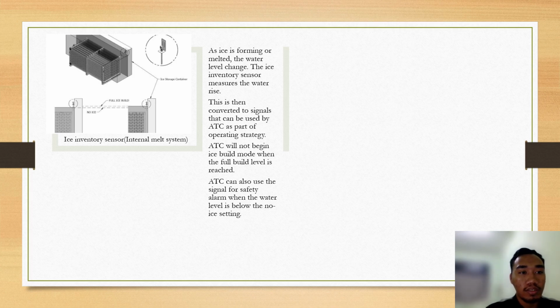And the last accessory is the ice inventory sensor for the internal melt system. As ice is forming or melting, the water level will change. The ice inventory sensor will measure the water rise. This is then converted to signals that can be used by automatic temperature control as part of the operating strategy. Automatic temperature control will not begin ice build mode when the full build level is reached. Automatic temperature control can also use the signal for a safety alarm when the water level is below the no ice setting.